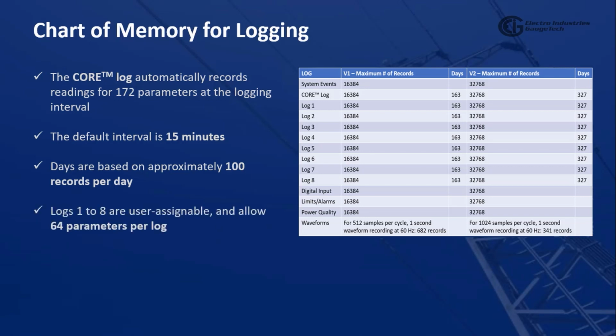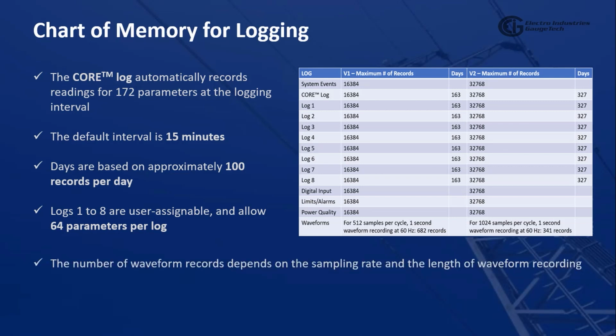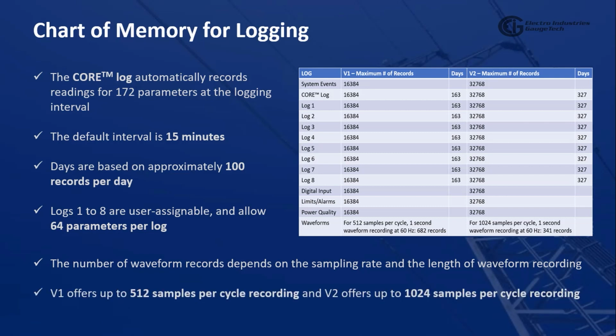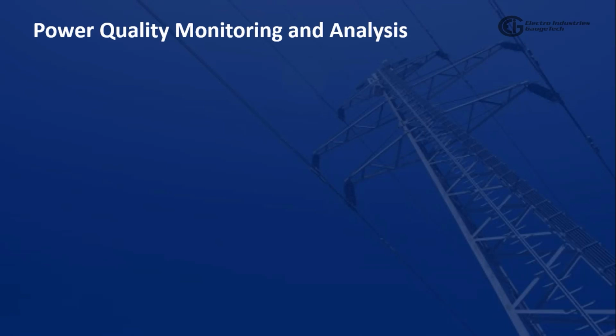Days are based on approximately 100 records per day. Logs 1 to 8 are user assignable and allow 64 parameters per log. The number of waveform records depends on the sampling rate and the length of waveform recording. V1 offers up to 512 samples per cycle recording, and V2 offers up to 1024 samples per cycle recording. After this, the next feature is power quality monitoring and analysis.